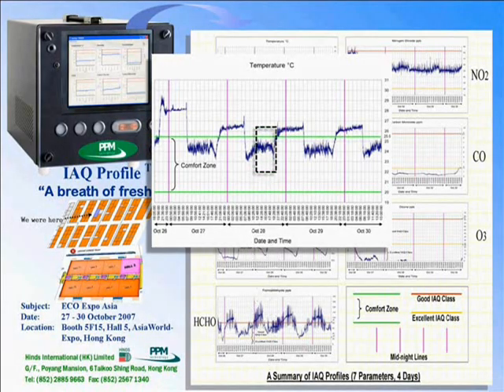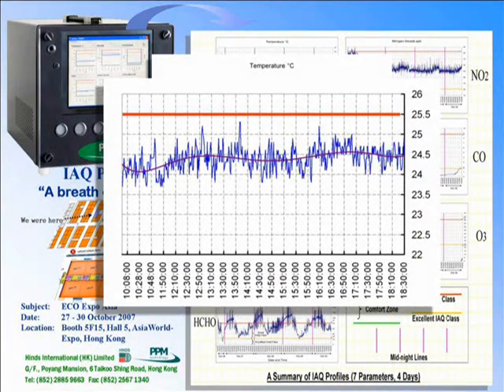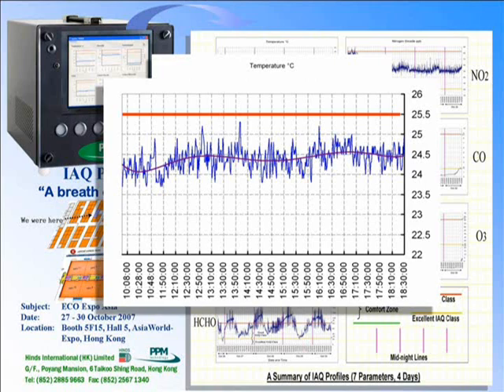If you want to magnify it, pick that section. Ten o'clock in the morning to half past six in the afternoon — the time people enter and the time people left. This red line represents the average, which the computer can draw for you. You can see that in a big hall with air conditioning, this red line stays between 24 to 24.5°C — very well controlled air temperature.